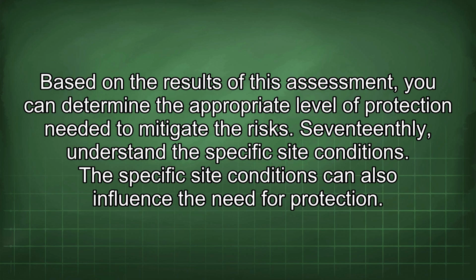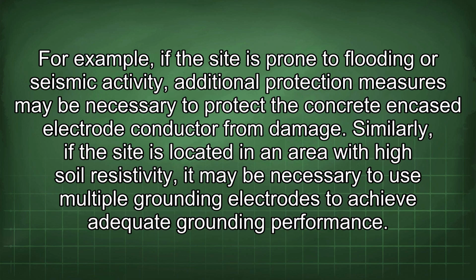17thly, understand the specific site conditions. The specific site conditions can also influence the need for protection. For example, if the site is prone to flooding or seismic activity, additional protection measures may be necessary to protect the concrete encased electrode conductor from damage. Similarly, if the site is located in an area with high soil resistivity, it may be necessary to use multiple grounding electrodes to achieve adequate grounding performance.